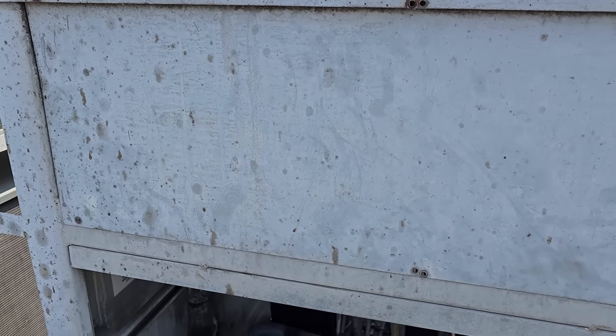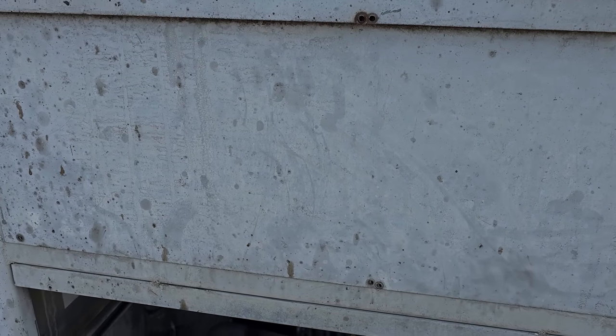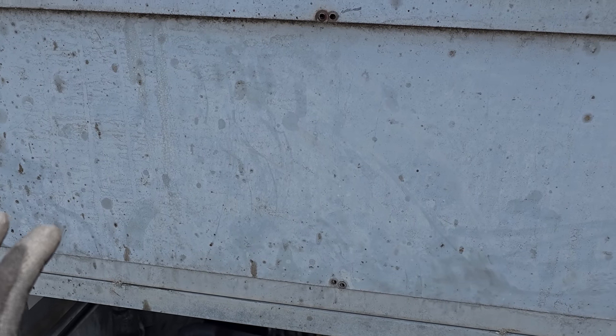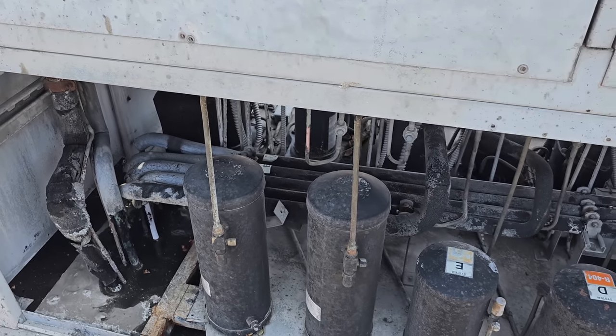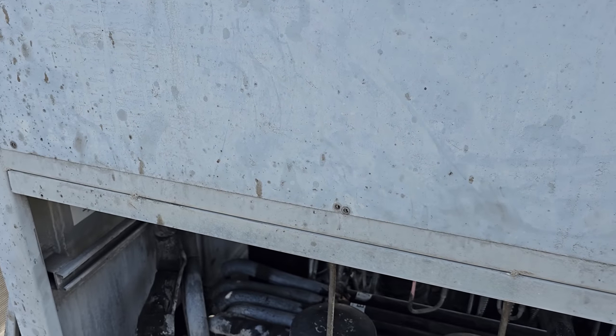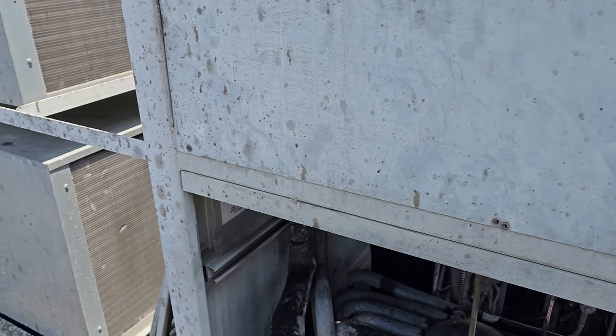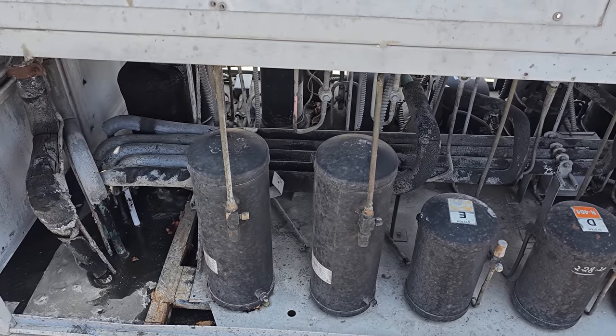And again, I'm not normally into bypassing them, but I'm still gonna talk them into taking this compressor out of this rack. So there's no point in replacing the valve. We're just gonna recover the charge, bypass the valve, because it's currently May 18th, and it's like 90 degrees this week and 100 degrees this weekend, and it's gonna be that way for the rest of the summer. So the head pressure control valve's not really gonna come into play. But even if it was, we will probably have a new condensing unit before we get that far, but we have to get them operational. So that's where we're at right now.